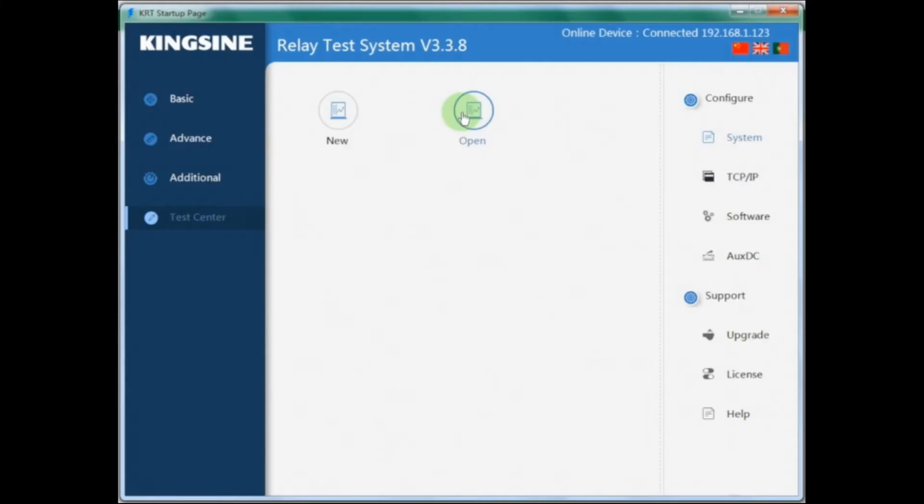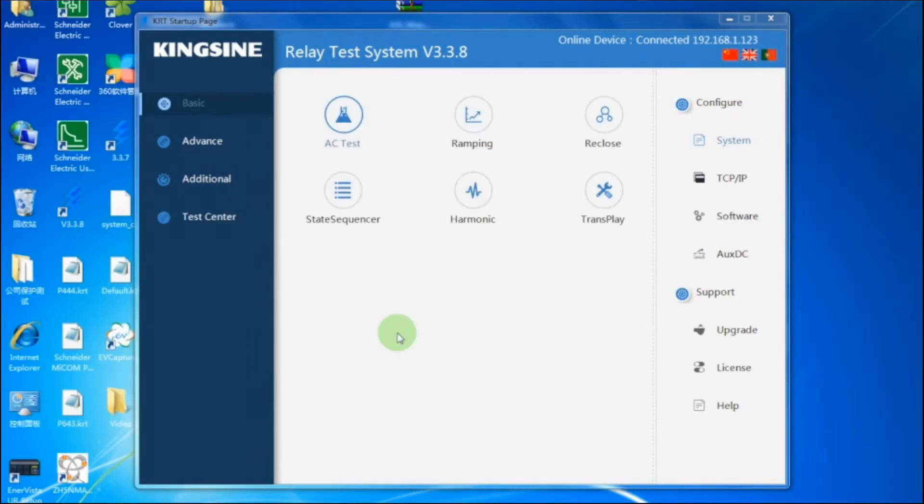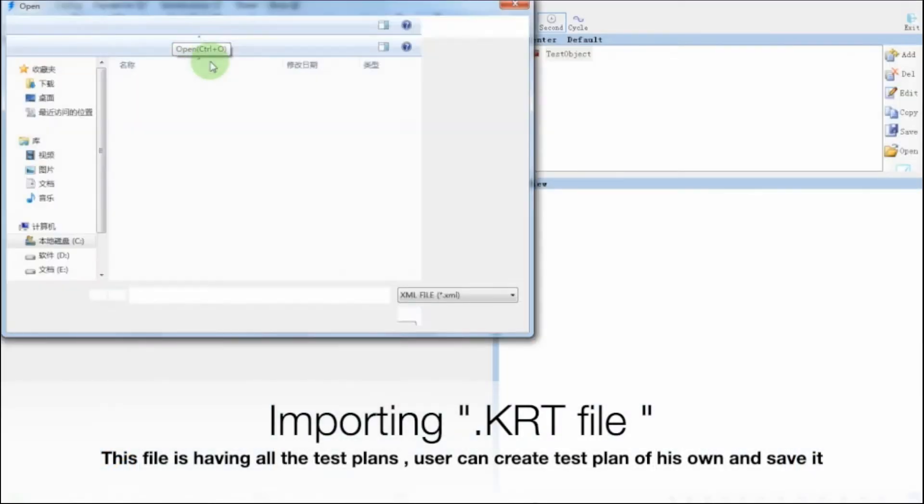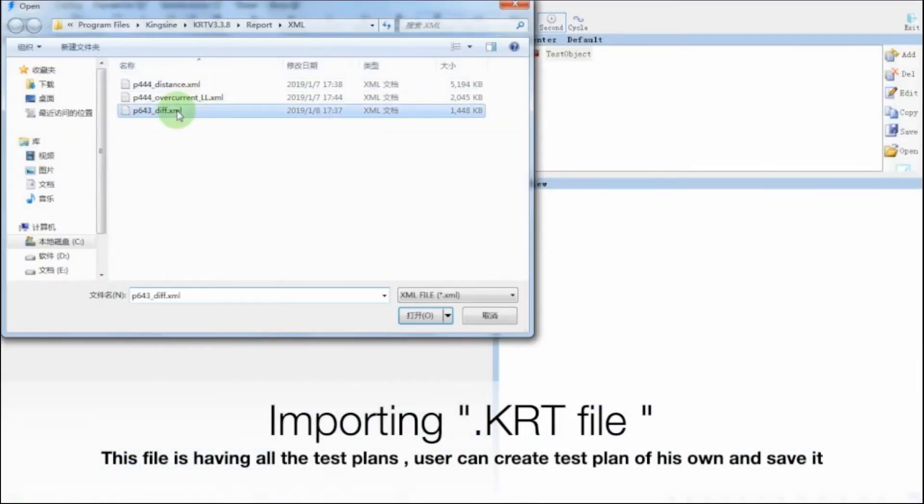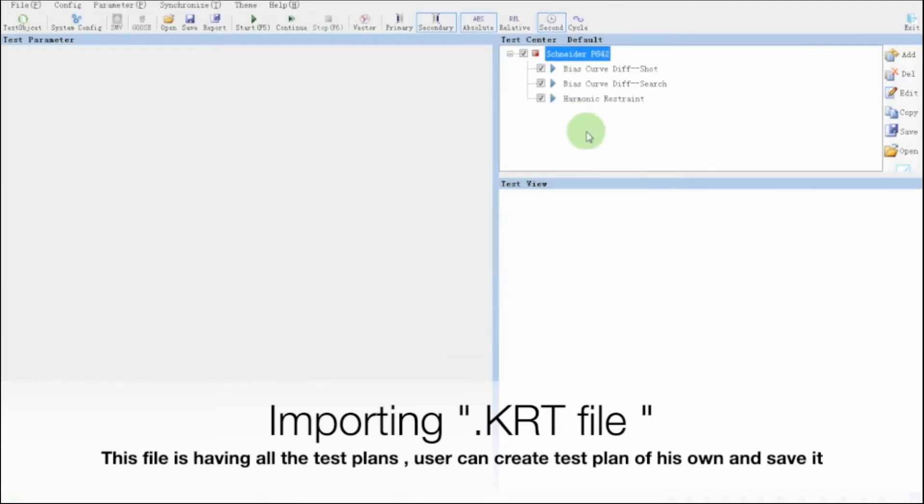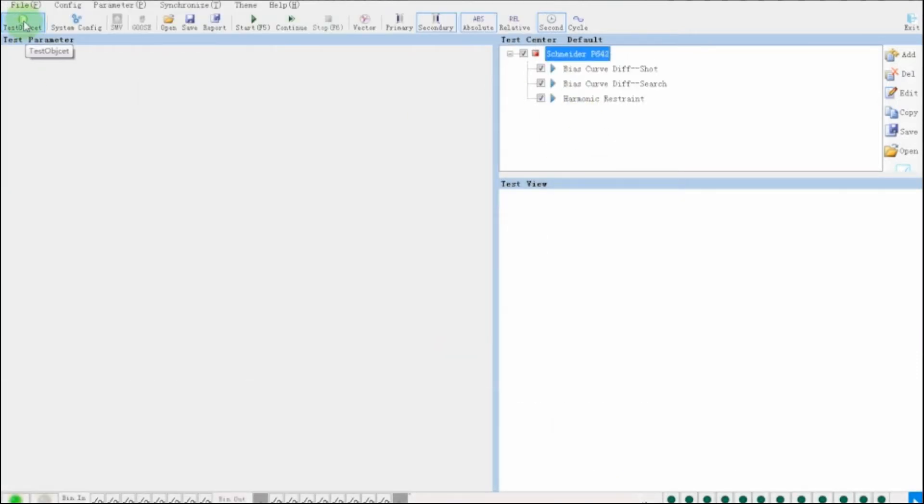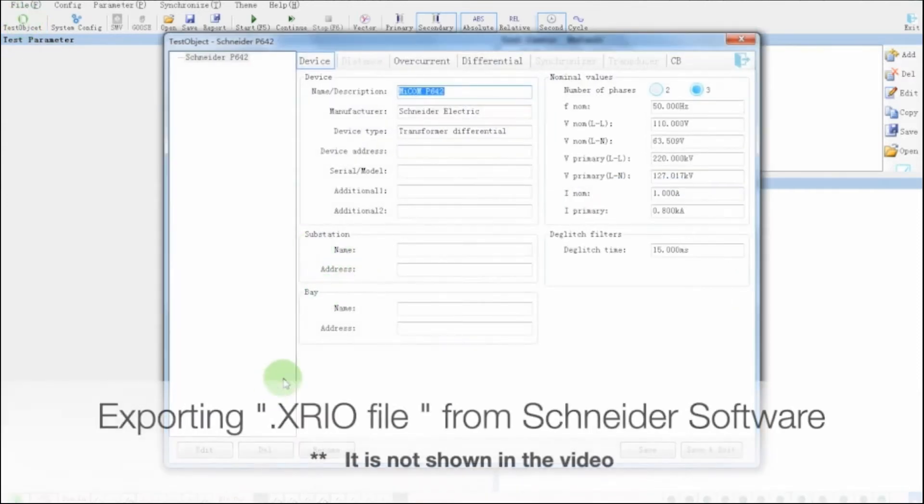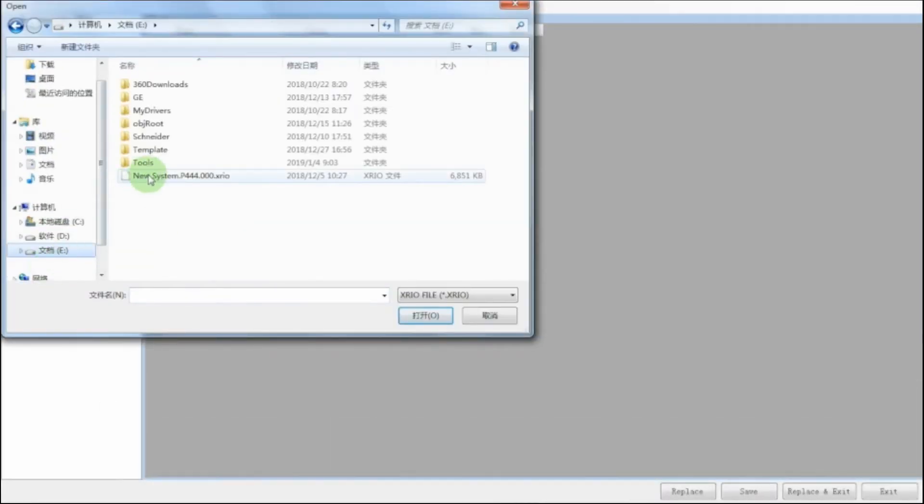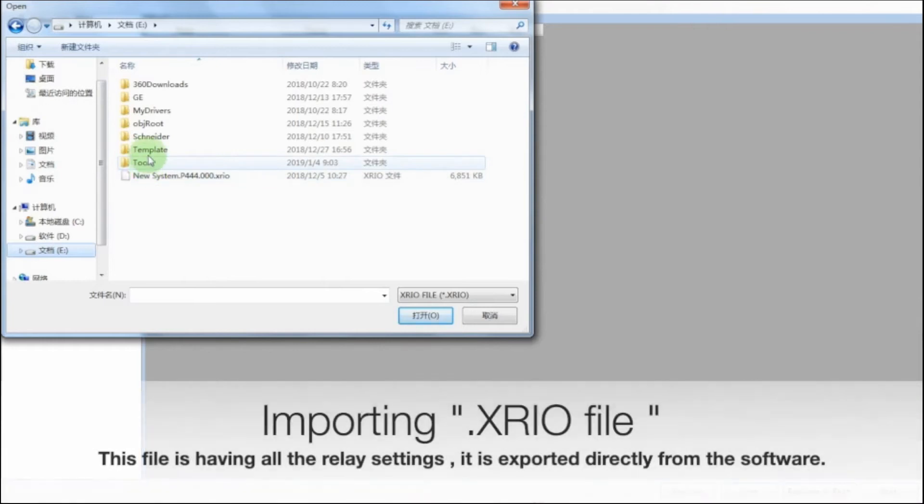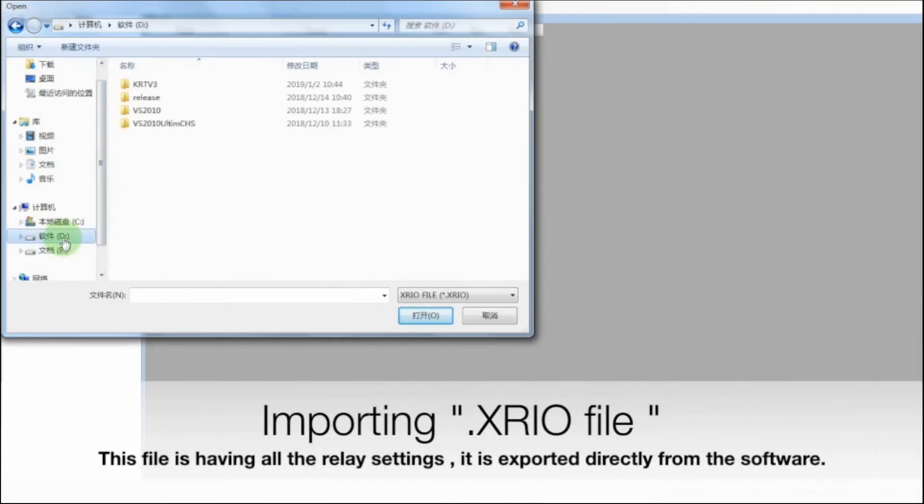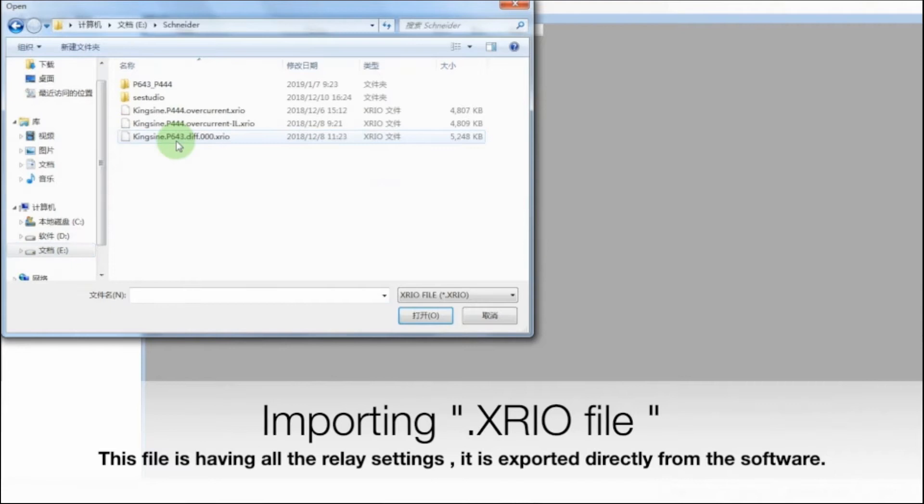To start with, we can click on Open and select test template from the template library. In this case, we will click on New to import KRT test file with existing test plan for differential relay P643. Let's now enter the Schneider software and import Xrio file format. We will enter the test object settings of KRT software and import that Xrio file, which we export from Schneider software.